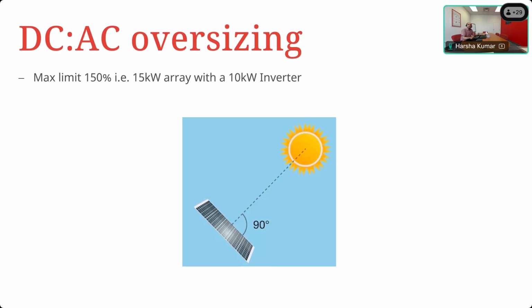Correct. A couple of questions here on the data manager. Is there still an A/B switch on the Gen24? No, that's a no. And then if the alignment of the strings is one east and one west, what could be the estimated oversizing rate? See, the oversizing is not per se dependent on the directions they face, it's the sum together. So if you've got an east and a west, we would recommend that you put them on separate MPPTs, but together you still have to keep them under the 150%. It's not about 150% at a particular time. It's 150% together.